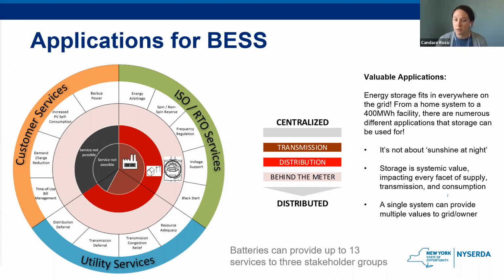Next, you have the spin or non-spin reserves. The spinning reserve is the generation capacity that is online and able to serve load immediately in response to an unexpected event, such as an unplanned generation outage. And then the non-spinning reserve is generation capacity that can respond to contingency events within a short period. So basically having that quick response time to anything that's abnormal going on in the grid.